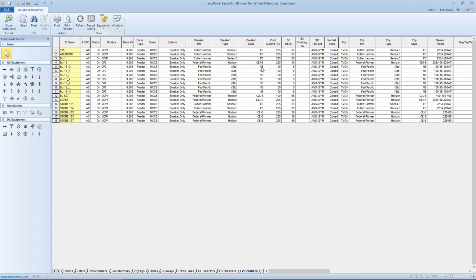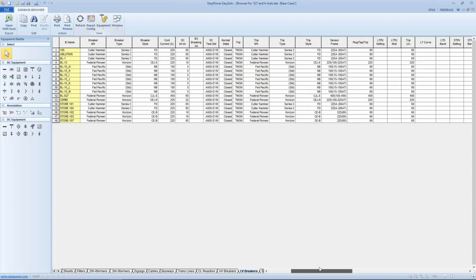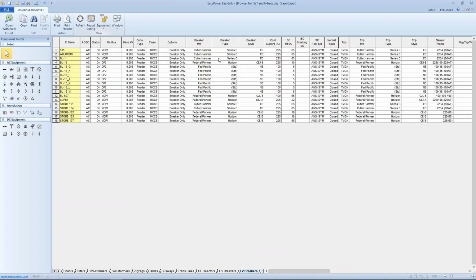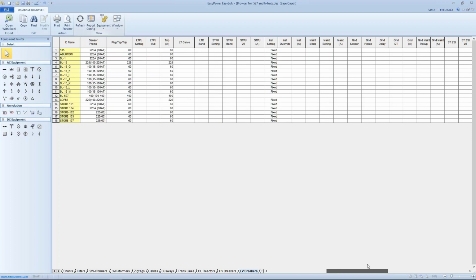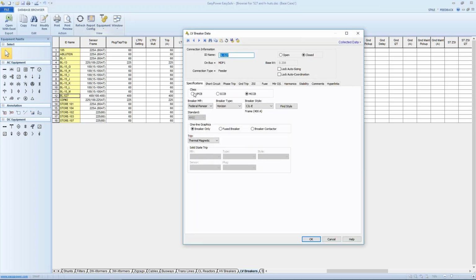The other thing I want to look at are my low voltage breakers. Again, what I'm looking for are missing blocks of data. Frequently this will be in the manufacturer, if we haven't designated a type or a manufacturer, and it looks like he has in all of these areas. The one that looks a little bit awry is we don't have values here for instantaneous settings, even though he has a manufacturer. Given that, we can go in and look for it just by double clicking on that yellow column.